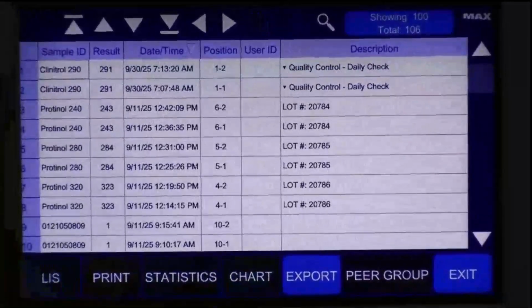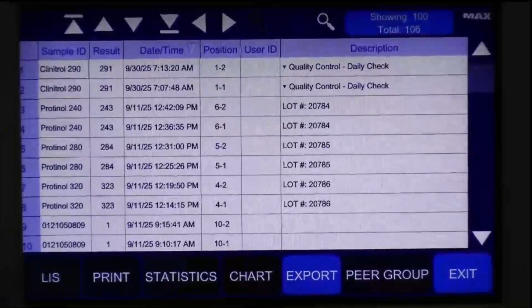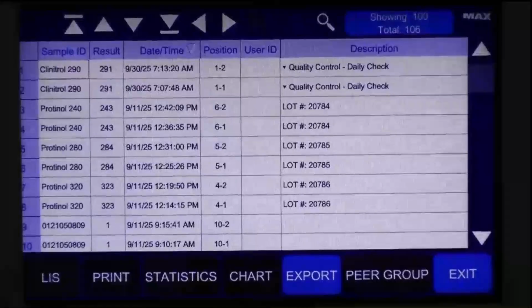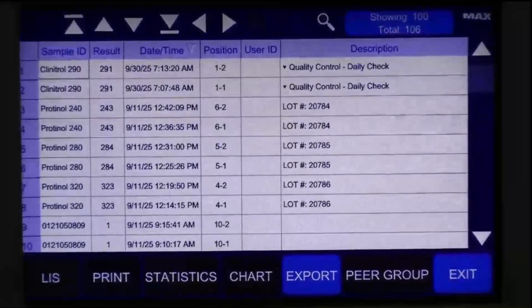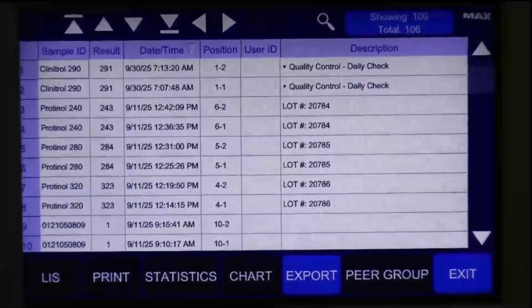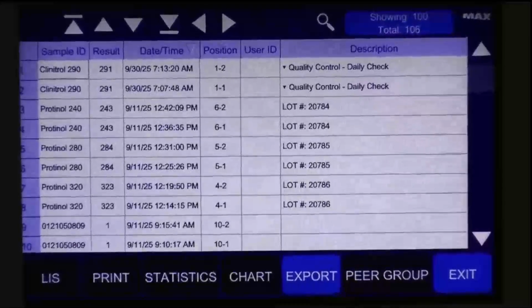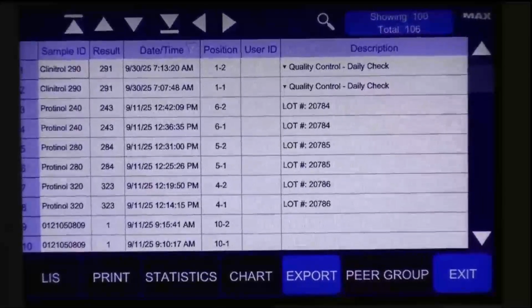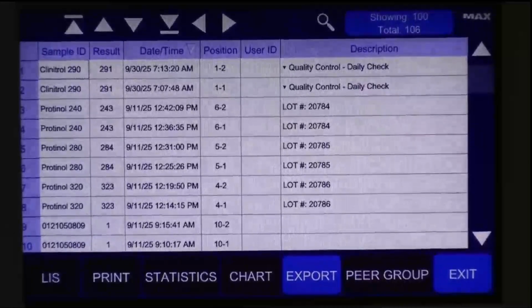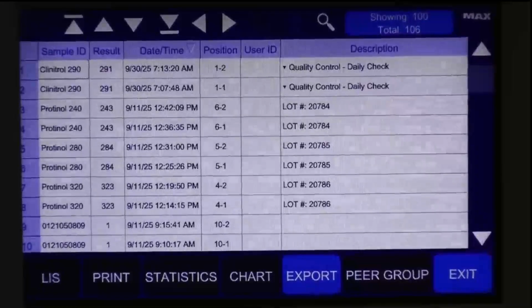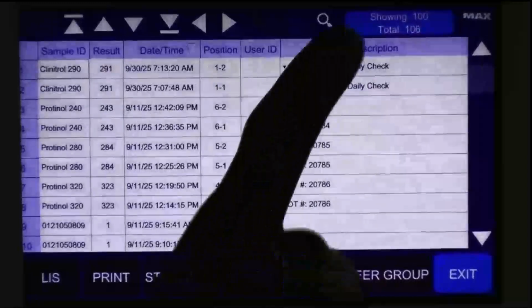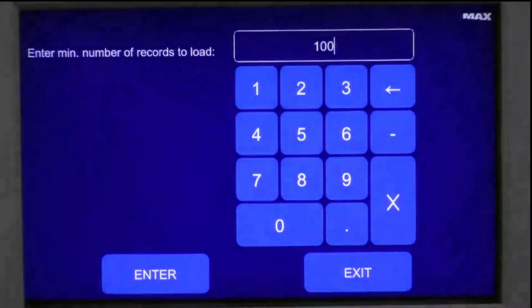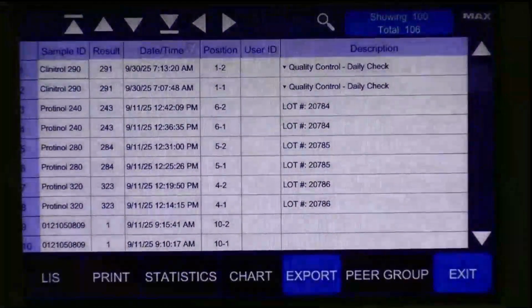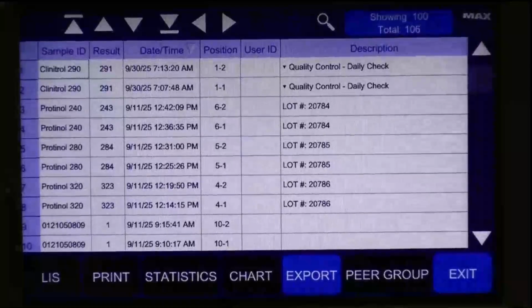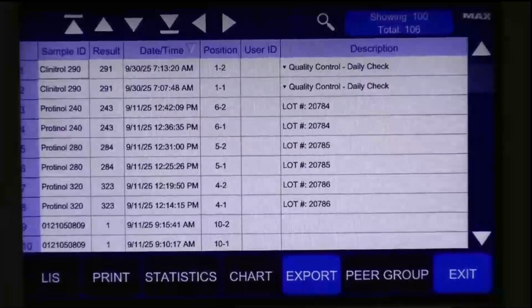And then here you're going to see this button that says peer group. What's cool about that button is if you take advantage of Advanced Instruments' Advanced QC Peer Group, which is a web-based platform that allows you to compare your quality control performance against peers who are also taking advantage of the Advanced QC Peer Group, then you can automatically transmit your QC results to the peer group by selecting the results and hitting this button right here. So you don't have to manually export them onto your jump drive and load them into the peer group manually. You can just hit that button and have everything cross over automatically. And there are several different filtering options up here for how many results you actually want to show. So you can modify all that before you transfer anything, either through the Ethernet port or by exporting onto an external drive.